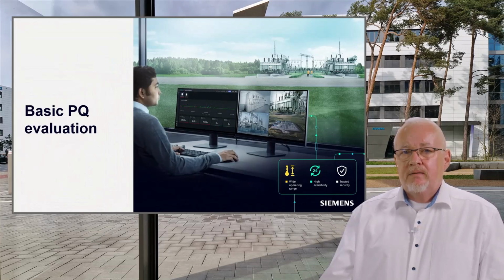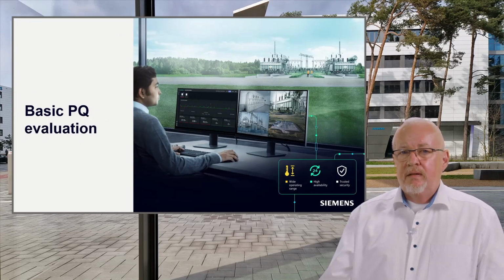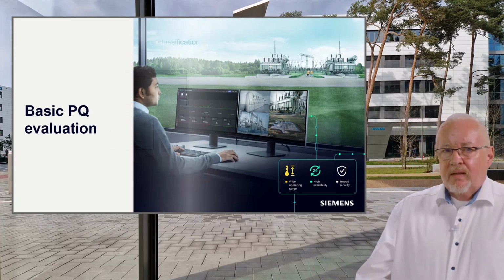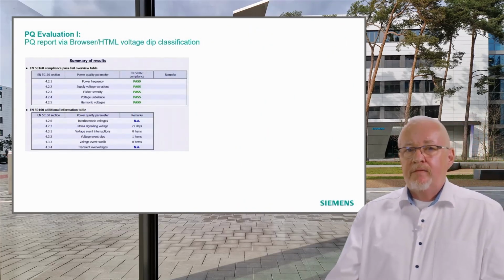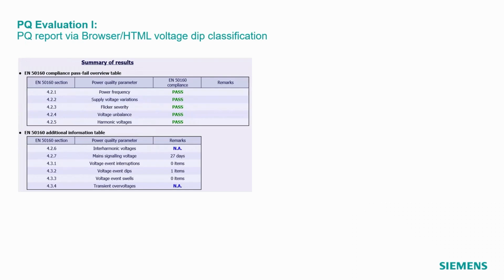So next I would like to go over to a basic power quality evaluation. I will show you a PQ report evaluation via browser, including a voltage dip classification. The devices provide a power quality report in the device itself. You can select an observation period, and then all the power quality phenomena are checked. And you see here in table 1 that all the continuous phenomena passed the evaluation.